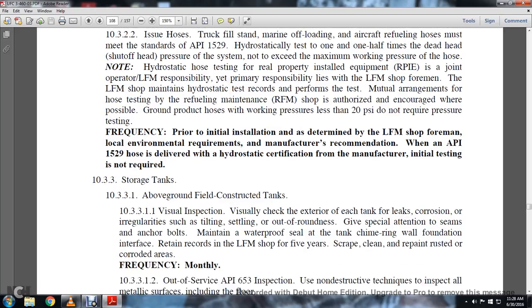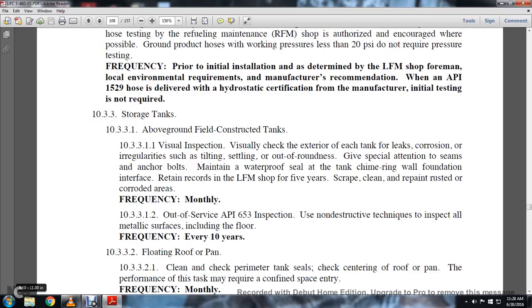10.3.3 Storage tanks. 10.3.3.1 Above ground field constructed tanks. Visual inspection: visually check the exterior of the tank for leaking, corrosion, irregularity, tilting, settling and out of roundness. Give special attention to seams and anchor bolts. Maintain a waterproof seal at the tank chime and ring wall foundation interface. Retain the record in the LFM shop for 5 years. Scrape, clean and repaint rusted and corroded areas. Frequency monthly.